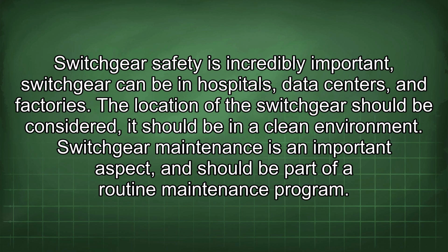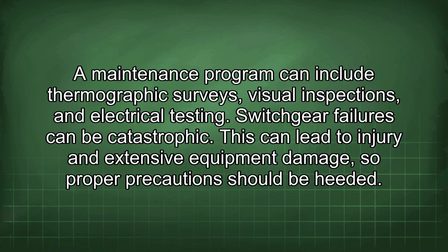The location of the switchgear should be considered. It should be in a clean environment. Switchgear maintenance is an important aspect and should be part of a routine maintenance program. A maintenance program can include thermographic surveys, visual inspections, and electrical testing.